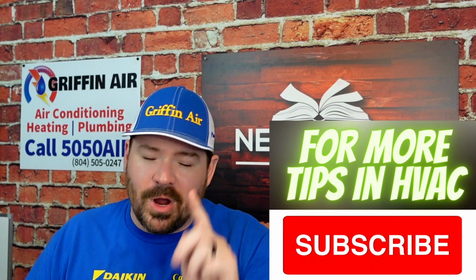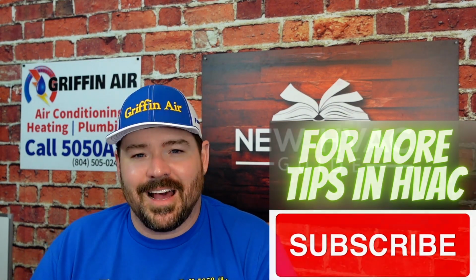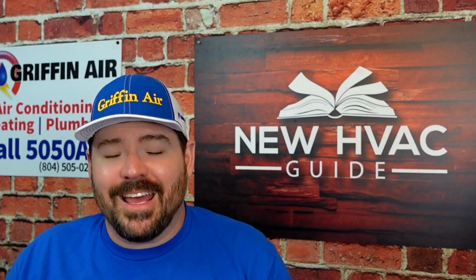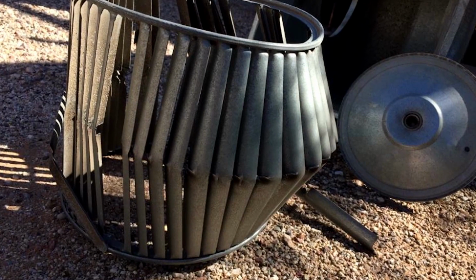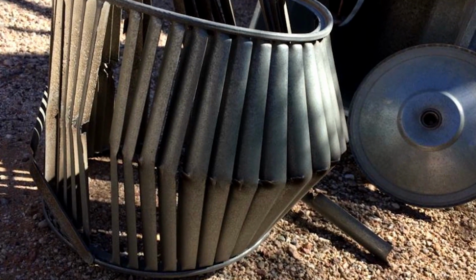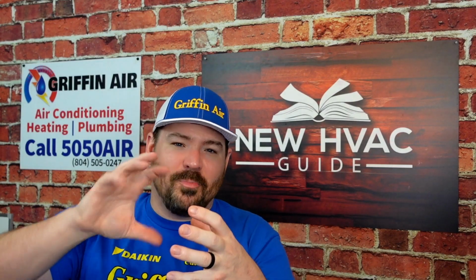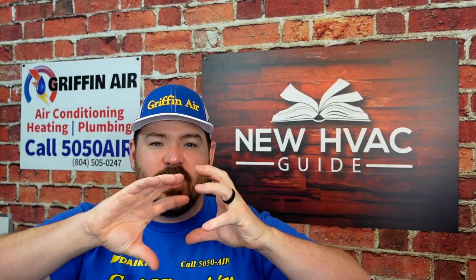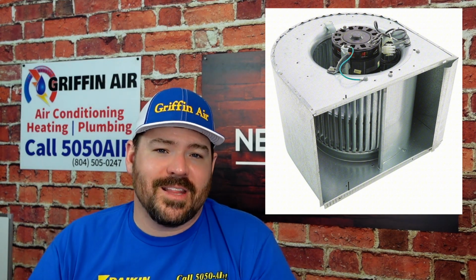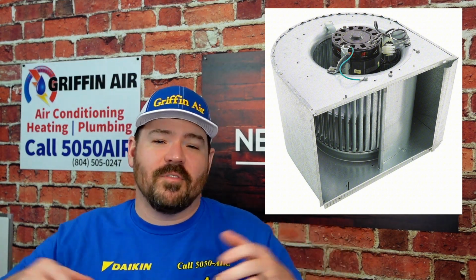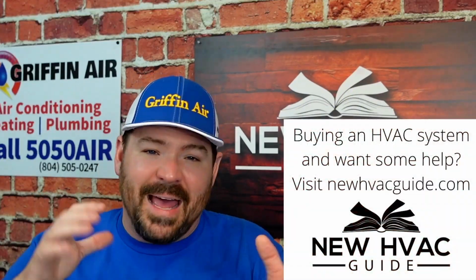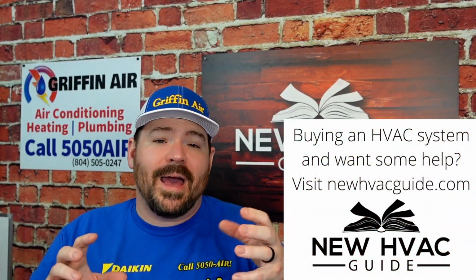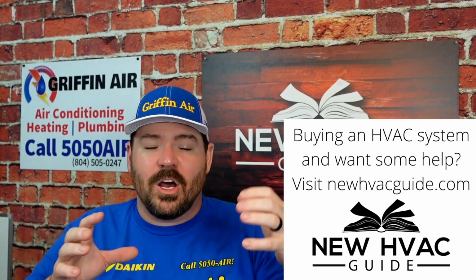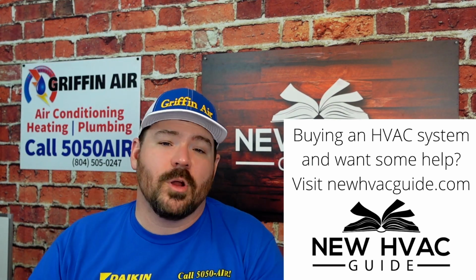Why are you having vibrations coming from your heating and air system? Let's dive into this. Number one, if you have a fan wheel that is bent, that is misshapen, that has come loose, you know, some of them I've even seen where the inner part of the entire fan wheel itself has kind of either separated or cracked. Any sort of problems with that fan wheel can cause vibrations in that heating and air system. In fact, I've seen some of them so bad that they start beating and banging up against the housing. Some of them get so bad that they actually get up against the housing and come to a screeching halt, which then can burn up your indoor fan motor.